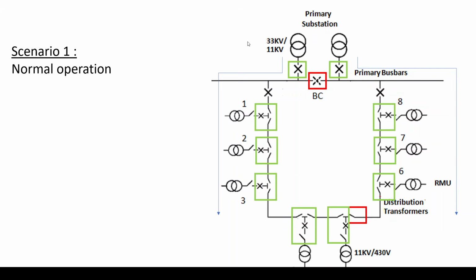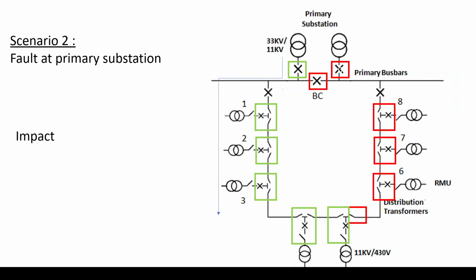Okay, so what would happen if a certain part of the network is faulty or goes down? So a certain scenario, let's call it scenario 2, a fault happens, for example, at the primary substation. So let's say a certain fault causes the feeder from this transformer to disconnect. So therefore, all this part of the network goes into red color. As you can see now, this section, due to any reason, due to any fault, is faulty and it trips, for example. So still my bus coupler was open. So the power, all of it is cut up to here, where I have assumed that my terminal, my RMU terminal is open.